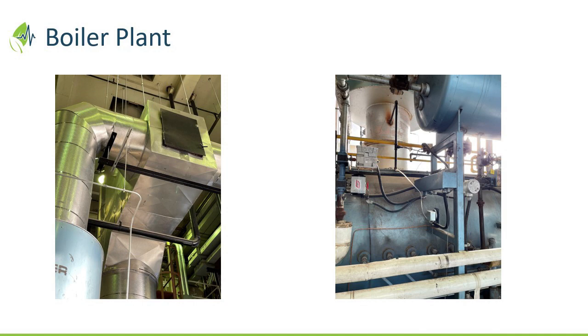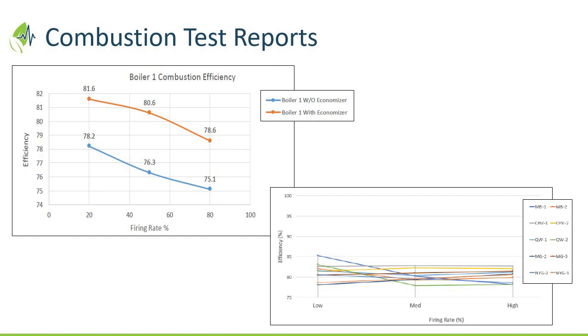Let me move this along because I'm conscious of the time. What you're hearing here is interesting technical stuff about improvements you could make: steam pressure, draft dampers, economizers, boiler sequencing. All of those things materially improve performance. The first step of 6 generated a 4% gas reduction. We're predicting, and we'll see how it turns out and what Julian's maths tells us, that we'll double that. So we're expecting that plant to get maybe 8-10% improvement, and through the summer even more than through the winter. So technically, everybody, you can check those things off on the checklist.